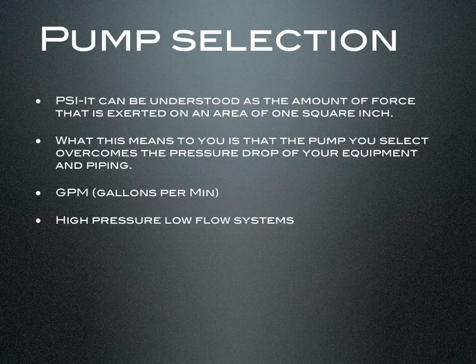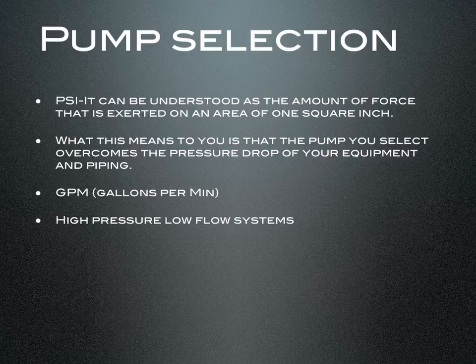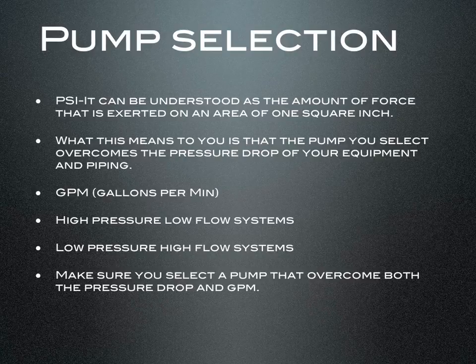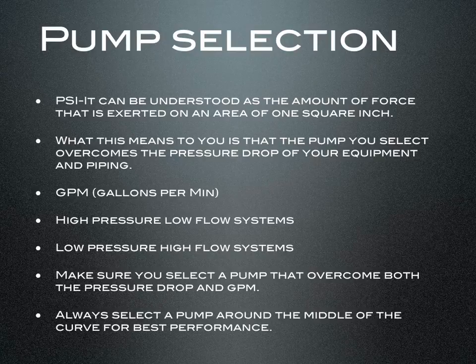There are different pumps for different types of processes. There are high pressure, low flow systems — for example, 40 PSI but only 3 gallons per minute, which we call high pressure pumps. On the other end of the spectrum, there are low pressure, high flow systems — maybe only 5 PSI but 50 gallons per minute. What's important is that you select the pump that overcomes both the pressure drop and gallons per minute. Always select a pump around the middle of the curve for the best performance. If you call our office, we'll help guide you through that.